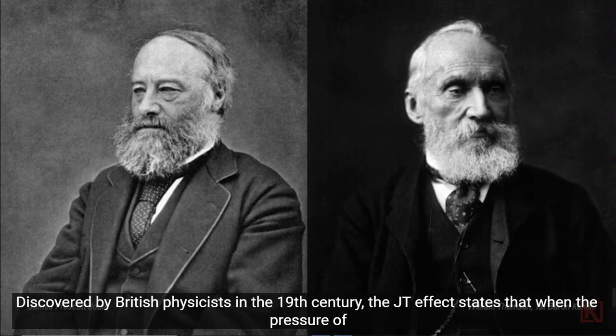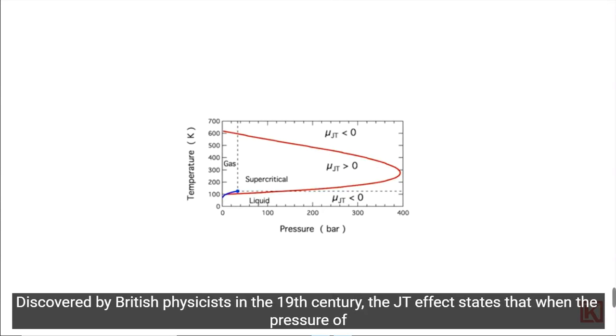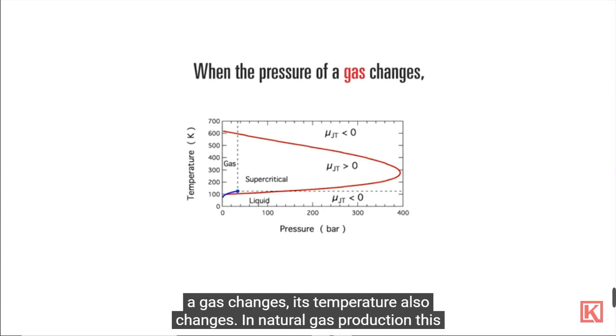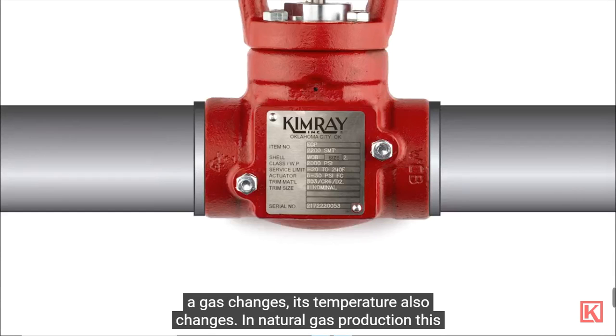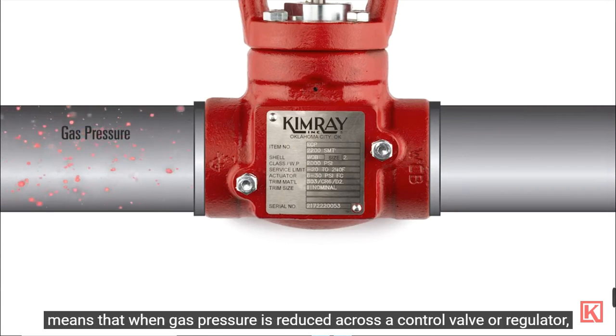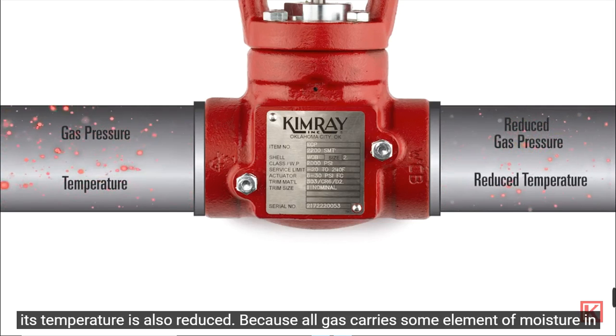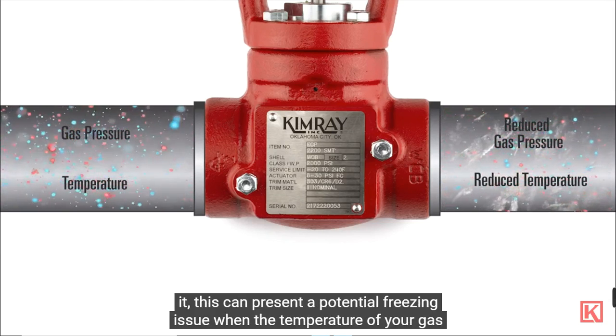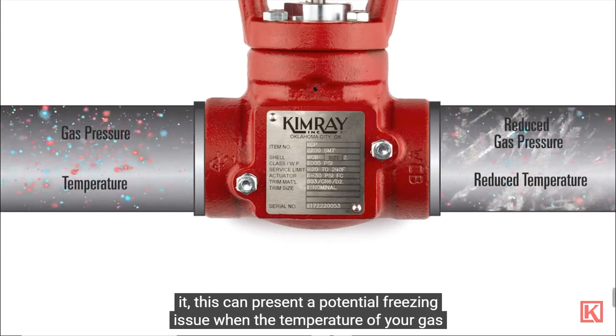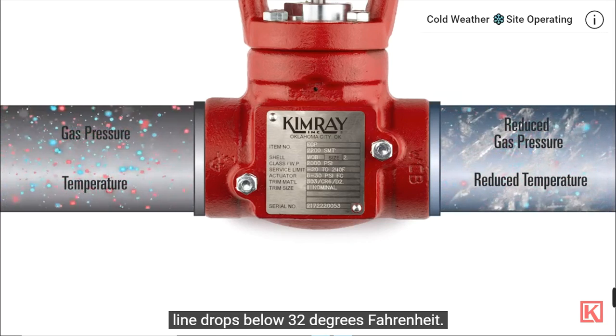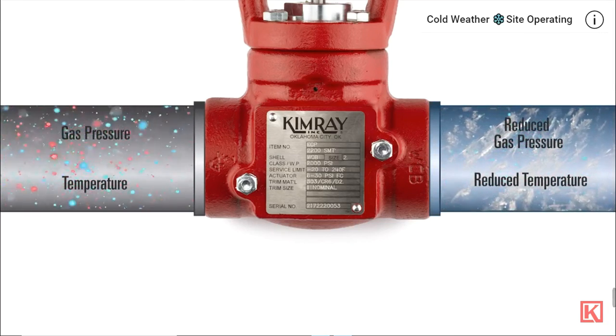Discovered by British physicists in the 19th century, the JT effect states that when the pressure of a gas changes, its temperature also changes. In natural gas production, this means that when gas pressure is reduced across a control valve or regulator, its temperature is also reduced. Because all gas carries some element of moisture in it, this can present a potential freezing issue when the temperature of your gas line drops below 32 degrees Fahrenheit.